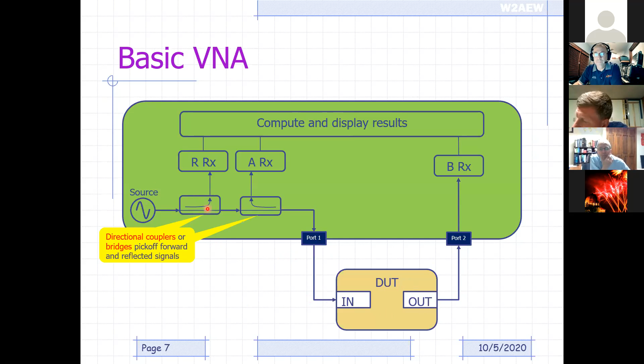Now, ideally, we're going to sample the signal that's being transmitted out to the device, essentially the source. So we're going to sample that in a receiver that we'll call R. And then any signal that is reflected off of that input port because of a mismatch will come back down this line and then be sampled by this coupler here. Okay. So we have these various receivers that measure the forward signal, the reflected signal, and the transmitted signal. And they measure both the magnitude and phase with respect to the source that's being generated.